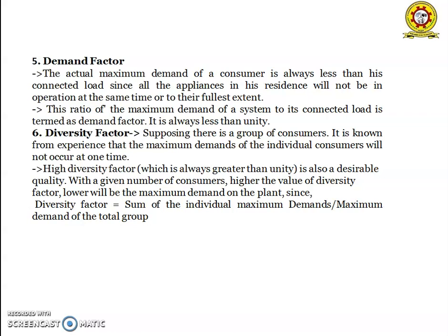Next, diversity factor. The higher the diversity factor, the lower will be the maximum demand on the plant for a given number of consumers, since diversity factor is equal to the sum of individual maximum demands by the maximum demand of the total pool.